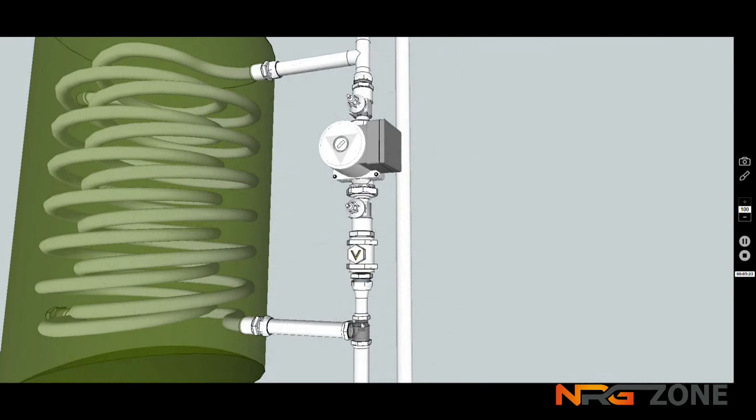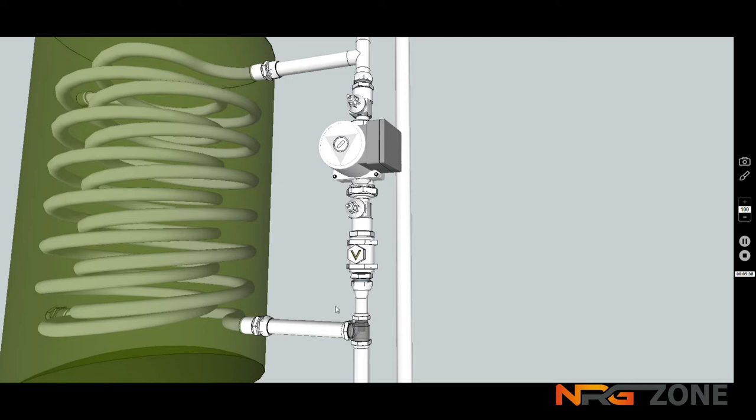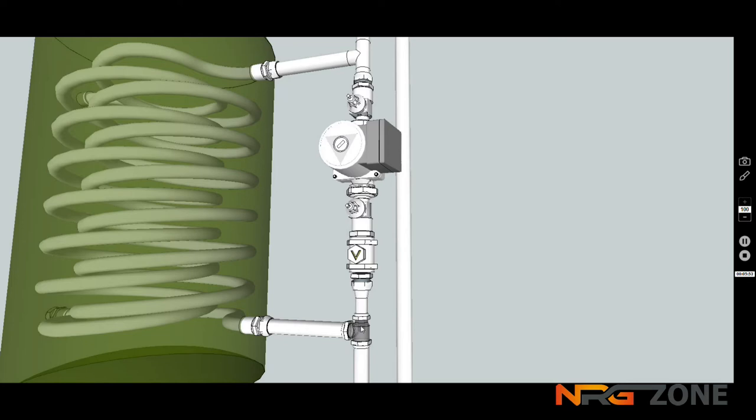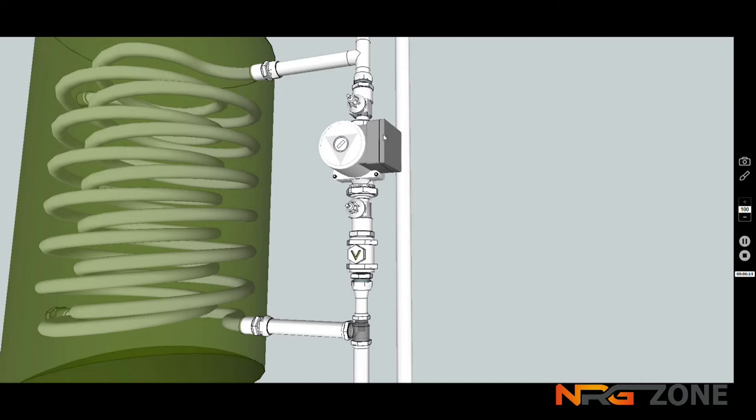At the injector T, there's a principle called the Bernoulli principle that comes into play. So, Bernoulli principle would be where water at a high velocity is pushed through, and then pushed through a restricted smaller tube or pipe, as is shown inside in this T. Injector Ts, you can purchase them from the local merchant, or you can actually make one. If you look, it's not a difficult concept. This injector travels just about halfway across the T. So, you inject the water from the pump here. What that does in effect is cause high pressure inside that injector, and as that opens out, the pressure reduces. As the pressure reduces, it actually causes a vacuum at this point.